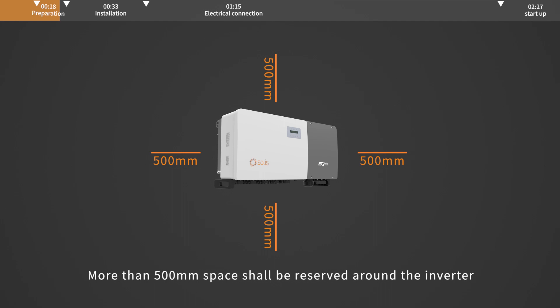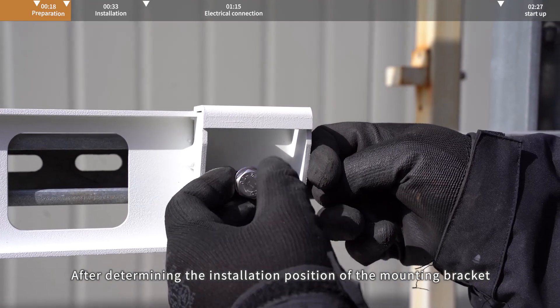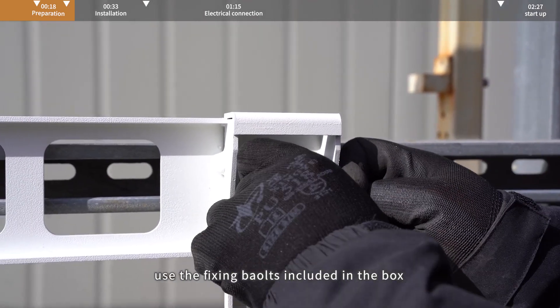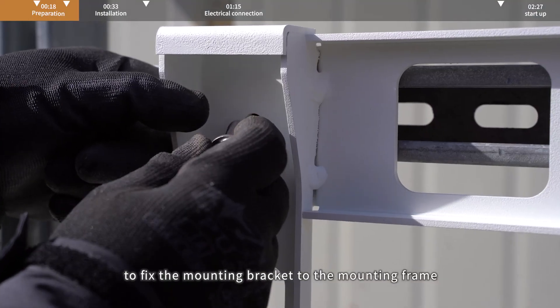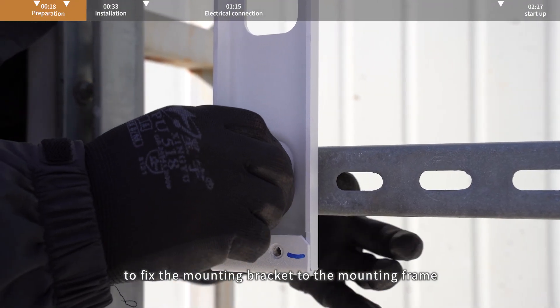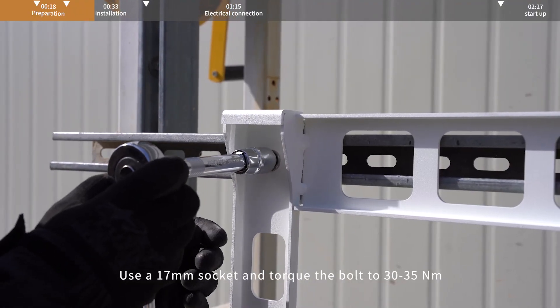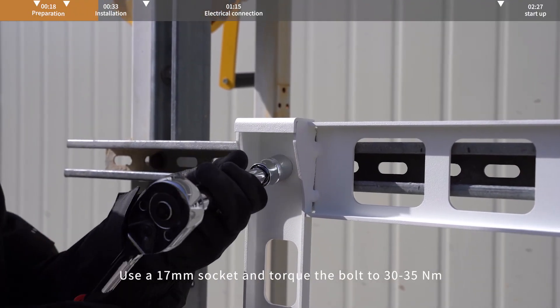More than 500 mm space shall be reserved around the inverter after determining the installation position of the mounting bracket. Use the fixing bolts included in the box to fix the mounting bracket to the mounting frame. Use a 17mm socket and torque the bolt to 30-35 Nm.